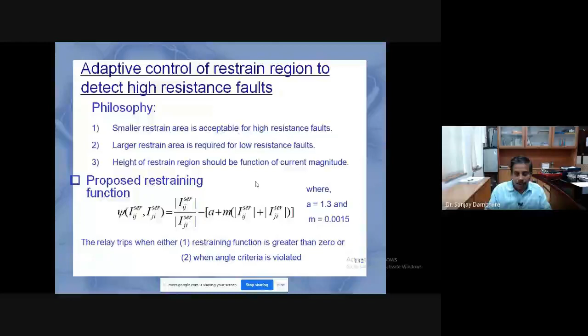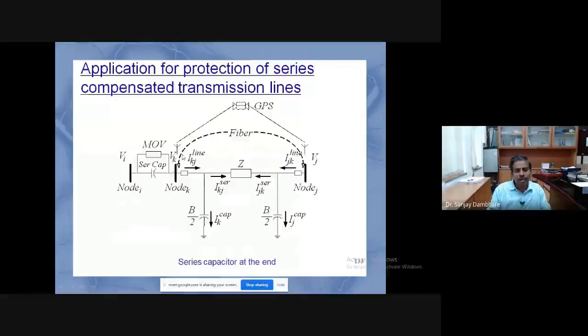We have seen that there is a problem with series compensation, like voltage inversion and current inversion, for which the distance relay maloperates. In those situations, your synchronized measurement unit can be put after the series compensator, and again you can implement the same algorithm.